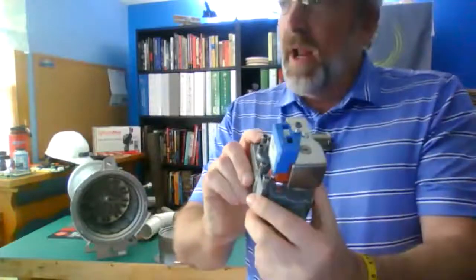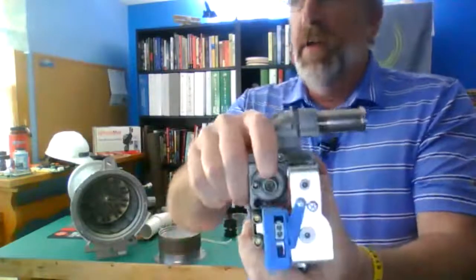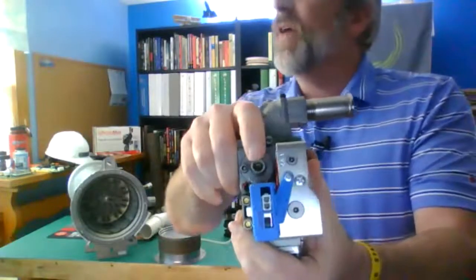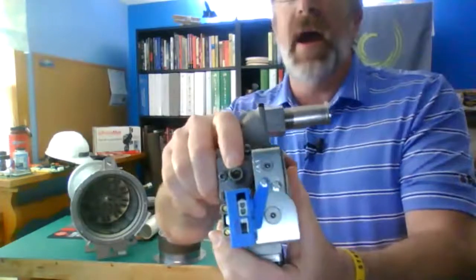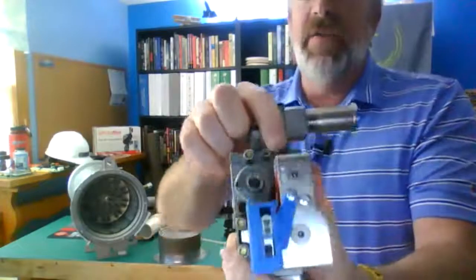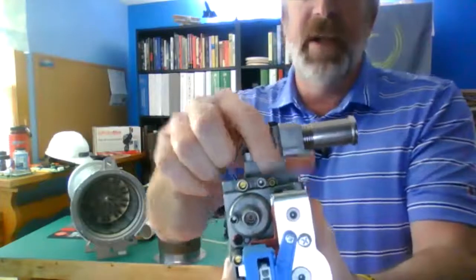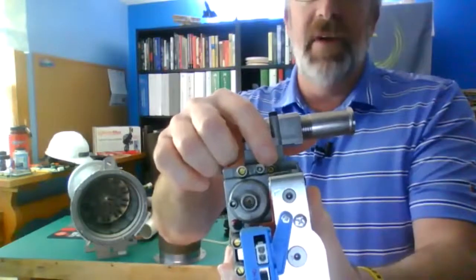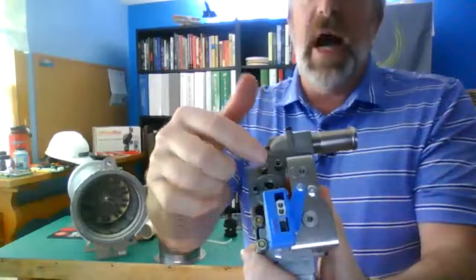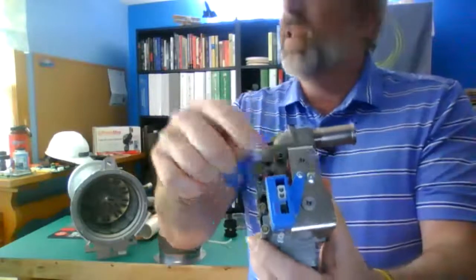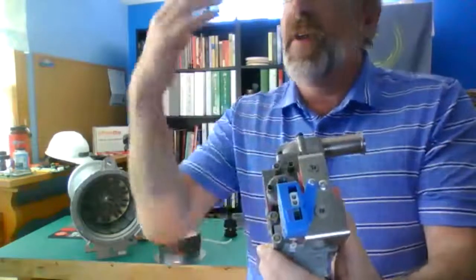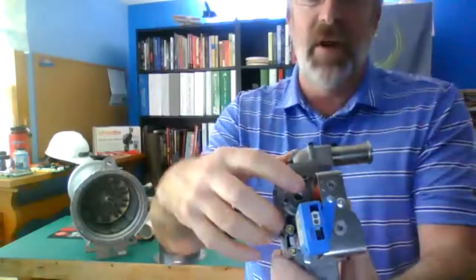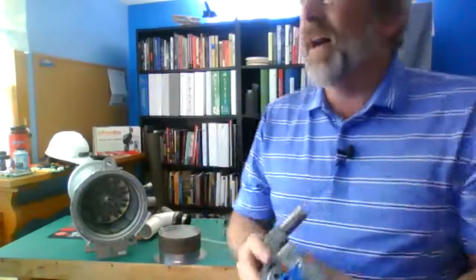Now, when I'm adjusting my gas valve, right here, this is the low fire adjustment. There's a 4mm Allen wrench inside of there. And then right over here, this is my high fire adjustment. I've got a 2.5mm Allen wrench right here. So with this gas valve, I like to start with a low fire adjustment, make that first. If everything was way off, that's where I'm going to start. And then I trim it out with the high fire.